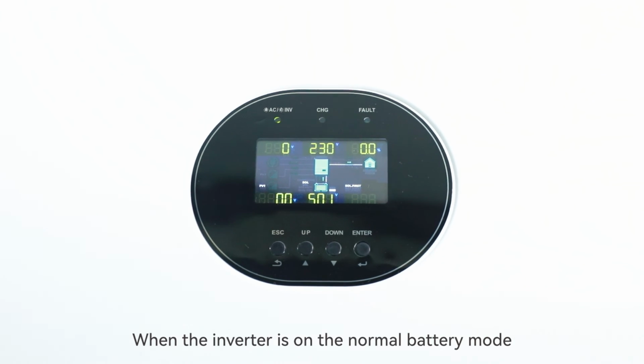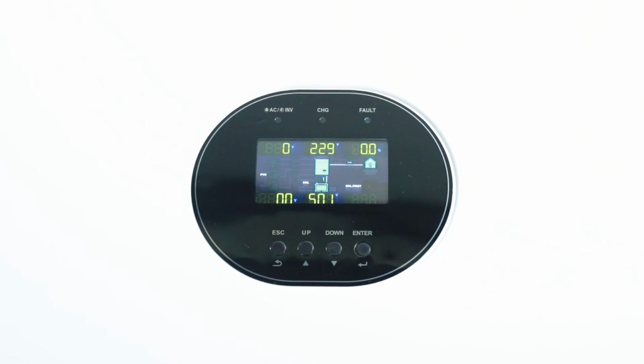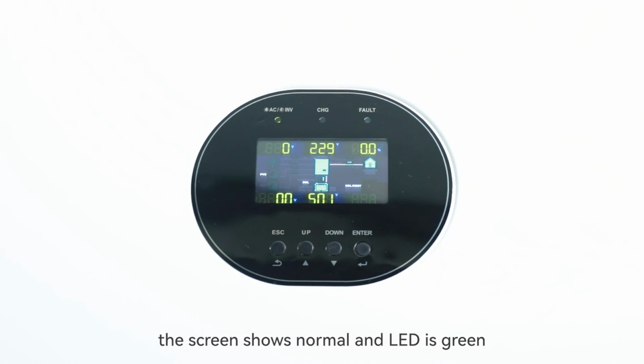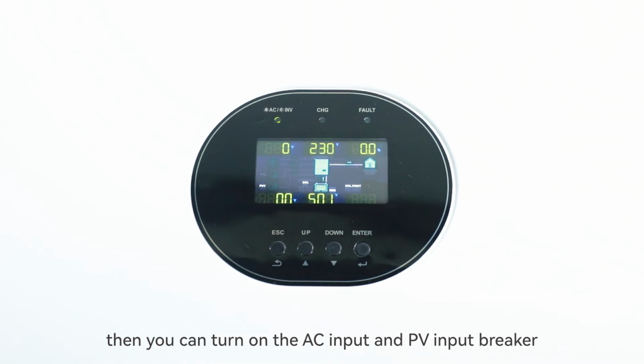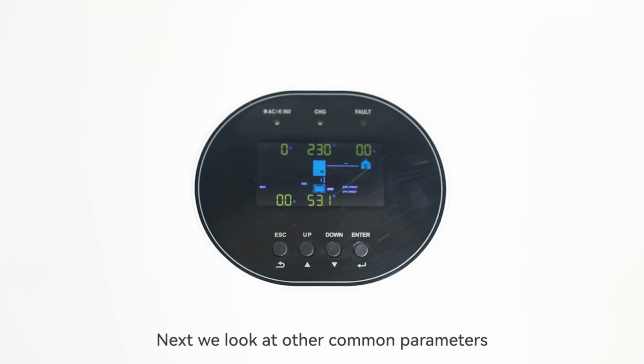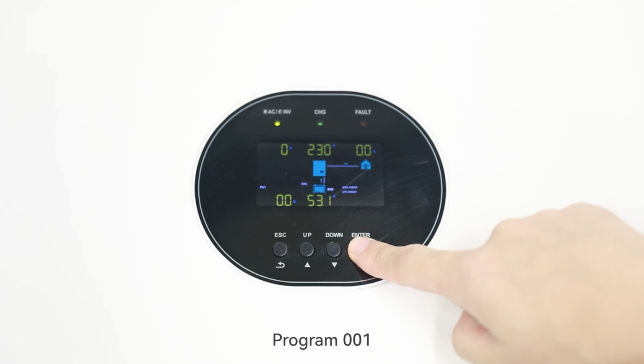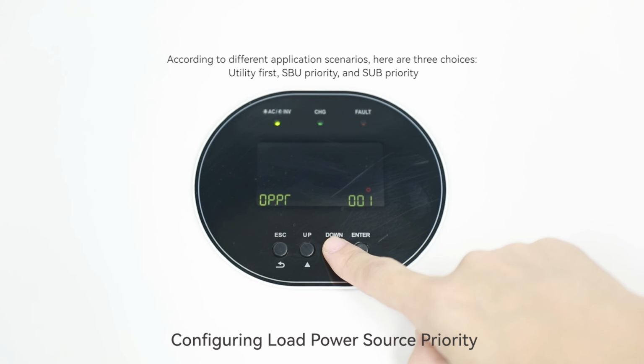When the inverter is in normal battery mode, the screen shows normal and the LED is green. Then you can turn on the AC input and PV input breaker. Next, we look at other common parameters. Program 001. Output source priority selection. Configuring load power source priority.